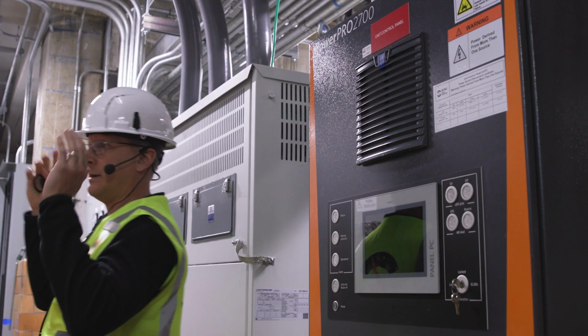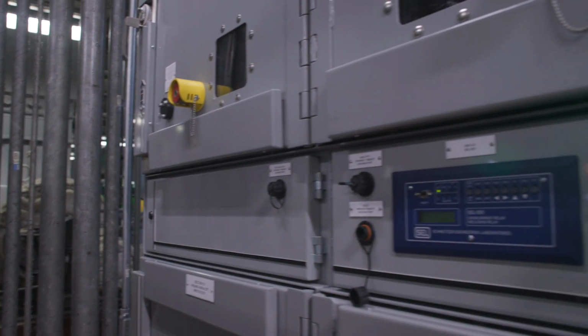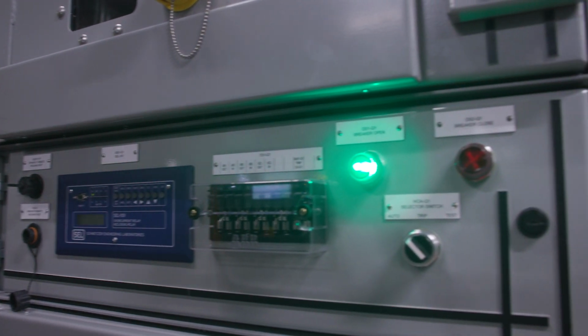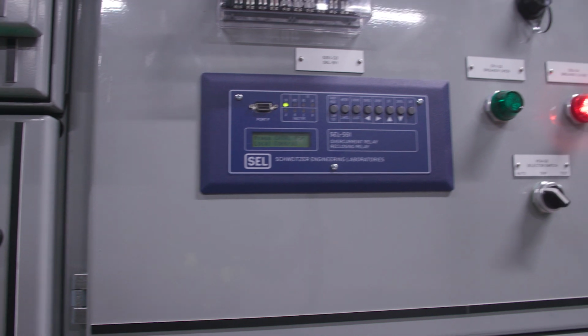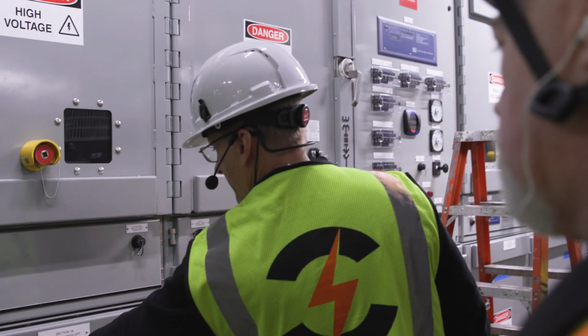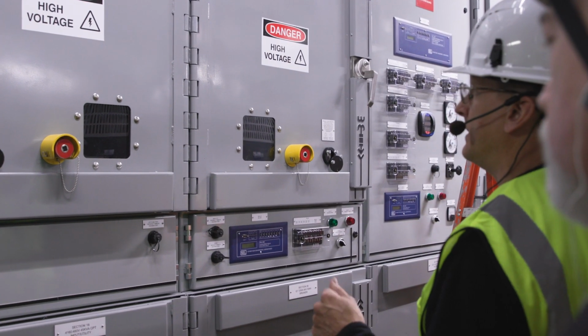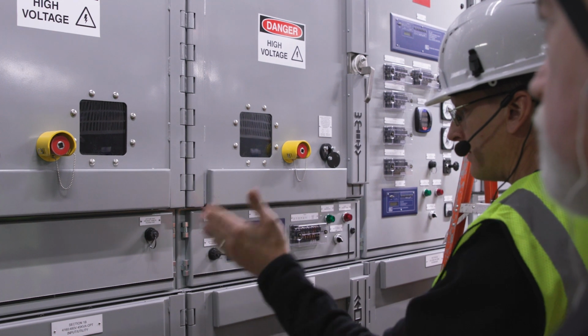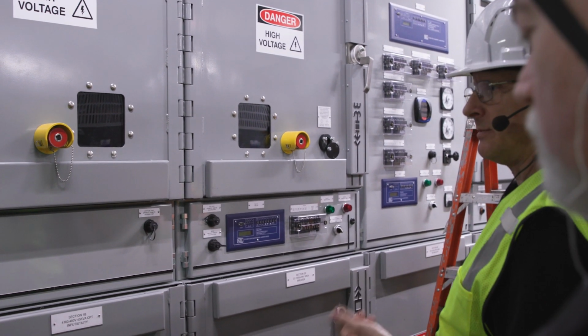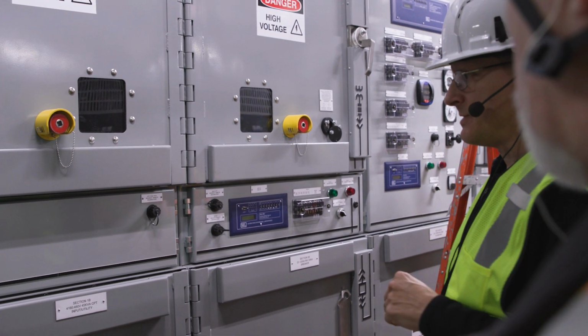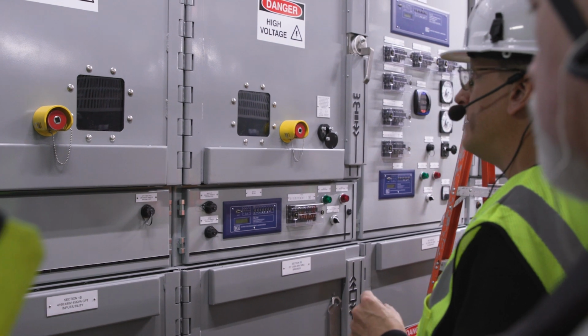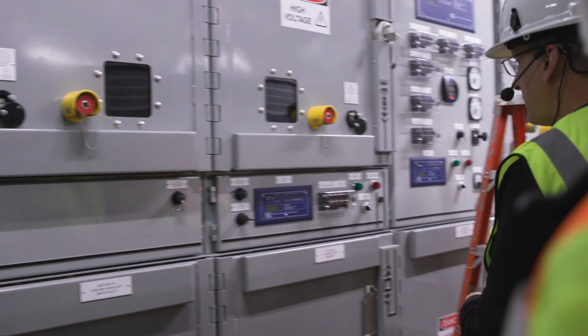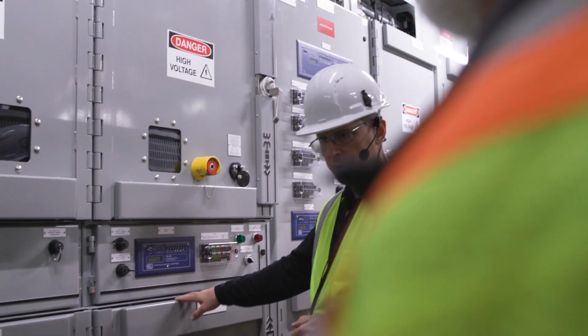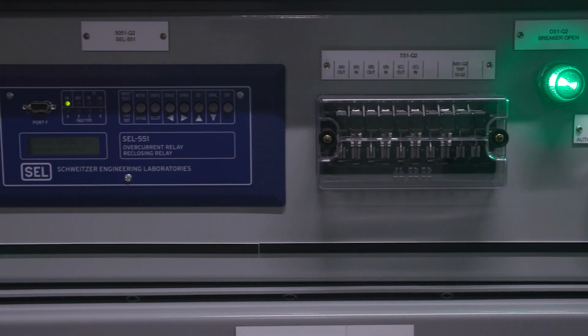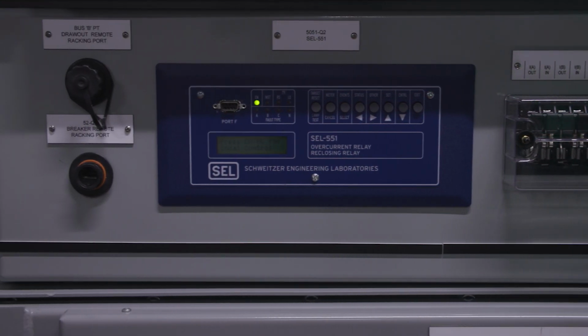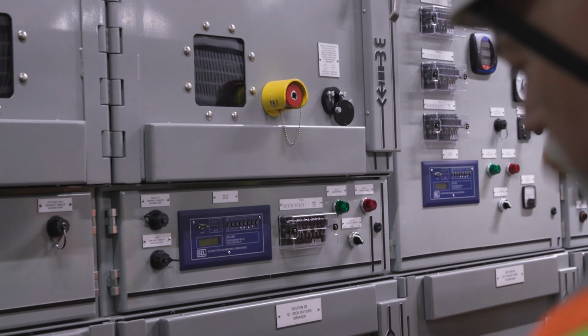Okay, right on the other side, this is our medium voltage switchgear. This is the medium voltage panel that houses all of our breakers. In this section, we have that 45 kVA CPT so that we can put some utility sourced power for 480 volts into our preheat, for example, or Prelube. It also provides utility power into our UCP so that we can power up the UCP if need be from utility alone. And we've got the other sections which contain the breakers themselves. So we've got our input breaker right here on the bottom of section 2. We've got also PTs on top, for voltage sensing as well. This is the PT for main sensing on top here.